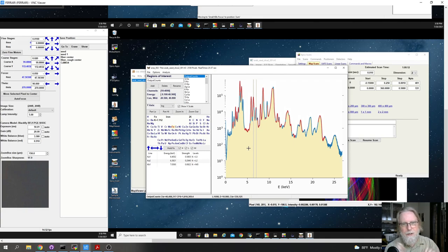If there's a current, you have to measure the height of that current or the voltage it makes. You might run that through an RC time constant in the oldest ways. So you need to measure the amount of charge that was collected for each of these 2 million x-rays per second. And so it takes a little bit of time. It takes about a microsecond or a little under a microsecond to be able to count that charge. And so there's a concern that it's difficult to tell two 7 keV photons from one 14 keV photon or two 5 keV from one 10 keV. So there's an effect called pileup where you can't tell the difference.